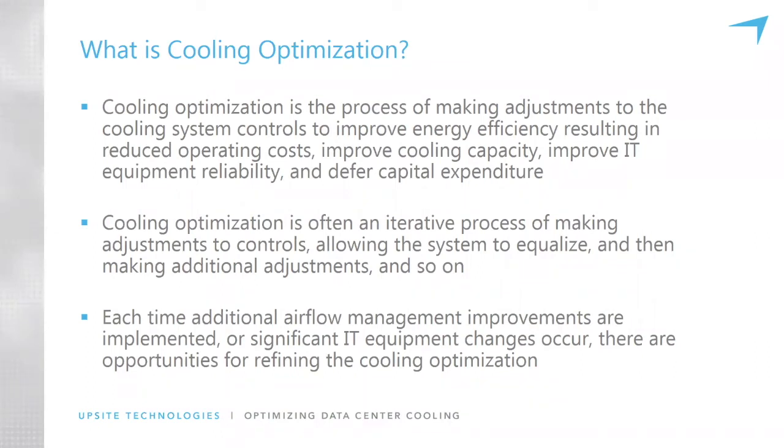There's many business cases where improved airflow management prevented the construction of either a new data center or a substantial remodel addition to an existing data center. And the value of the savings of deferring those massive capital expenditures can be enormous. Or even if it just means deferring the capital expenditure for buying another cooling unit. Most data centers have way more capacity than they need. It's just a question of utilizing that capacity that's already been installed more appropriately.